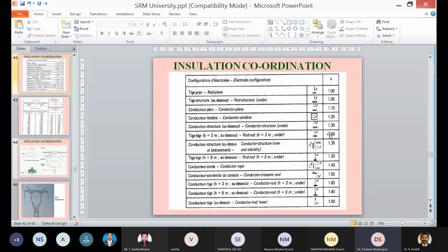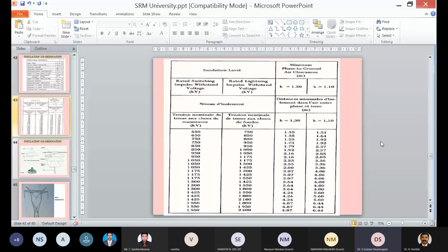When I say distance, it means phase to phase and phase to earth, or line to earth. And preferably in India, we go with the rod configuration, that is 1.30 times the actual value. How this 1.30 plays a major role, I will show you in the next slide.